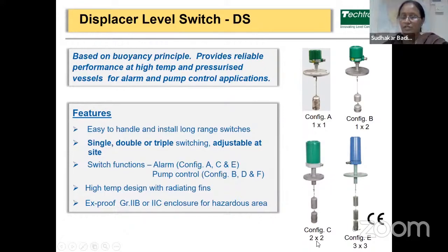Below it is configuration C, that is 2x2, that is two displacers with two switches. Then on its right side, it's configuration E, that is 3x3, that is three displacers and three switches. And this is configuration B, that is 1x2 with a split displacer. Here you can see the displacer is the smaller one. And this switch can be used for pump control applications. Basically, this is designed for pump control logic.